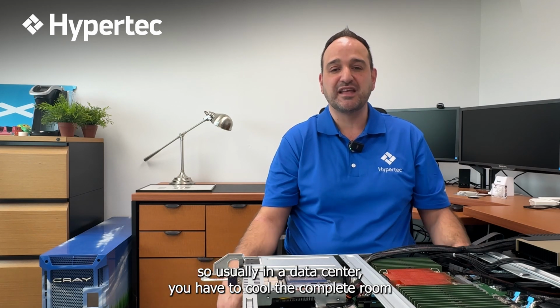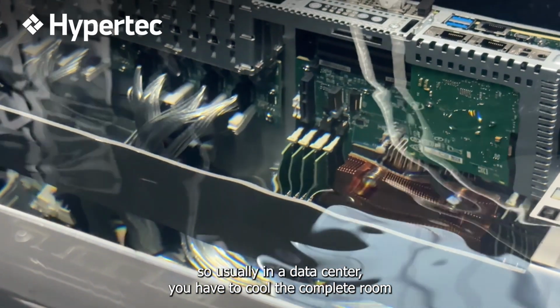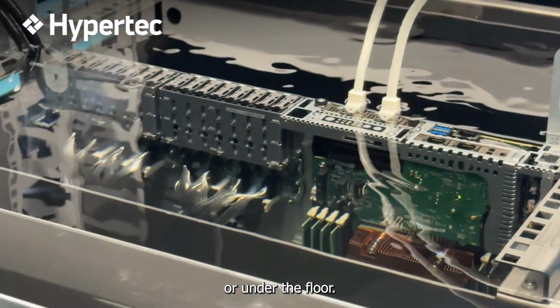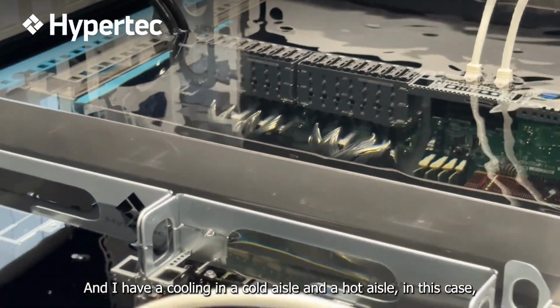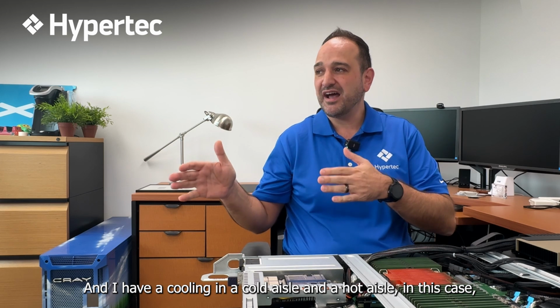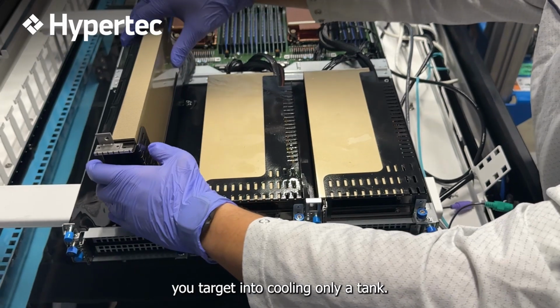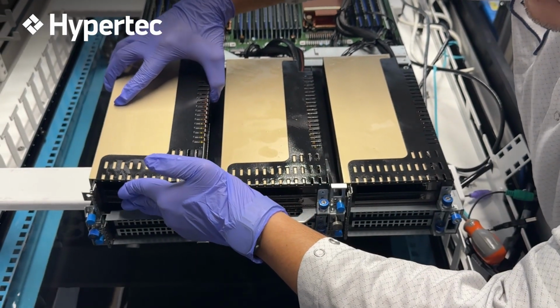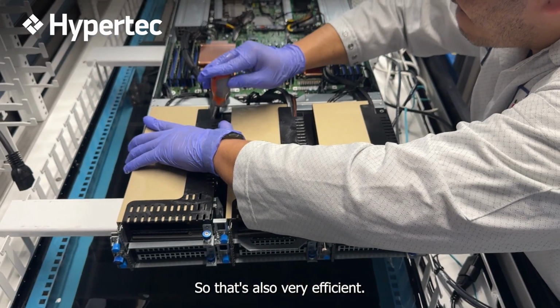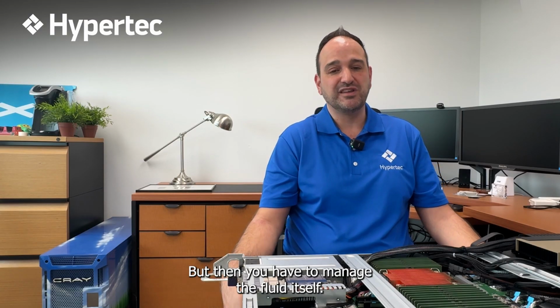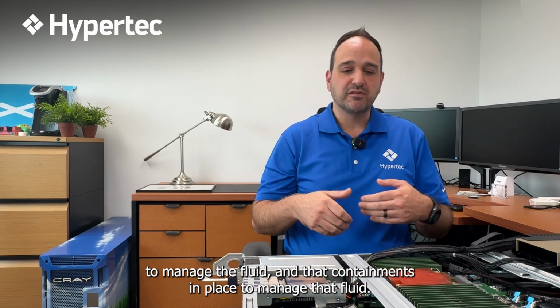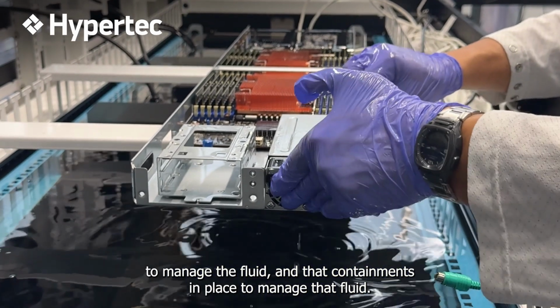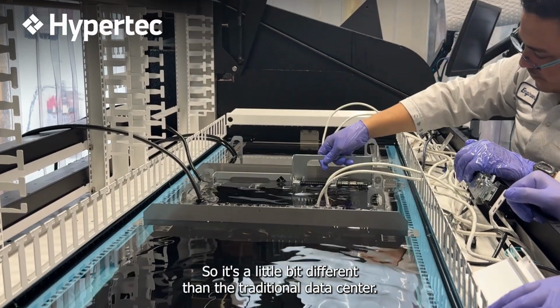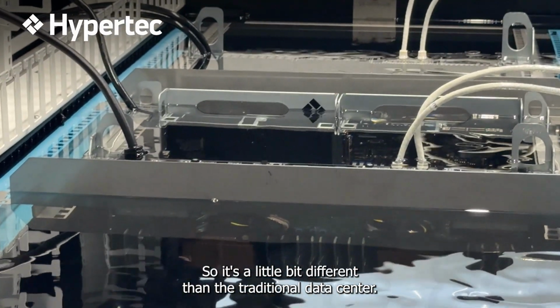In a standard data center, you usually have to cool the complete room or under the floor, with a cold aisle and a hot aisle. In this case, your target is cooling only a tank, so that's also very efficient. But then you have to manage the fluid itself — having fluid needs a protocol and containments in place to manage it. So it's a little different than the traditional data center.